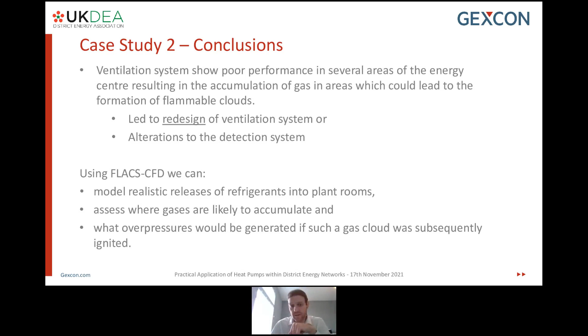So by using FLACS-CFD in this particular case, we can model more realistic releases of refrigerants into the plant rooms, assess where gas is likely to accumulate, and, if the gas is flammable, what overpressures would be generated upon ignition of that gas cloud.